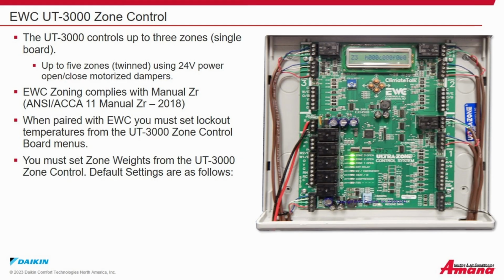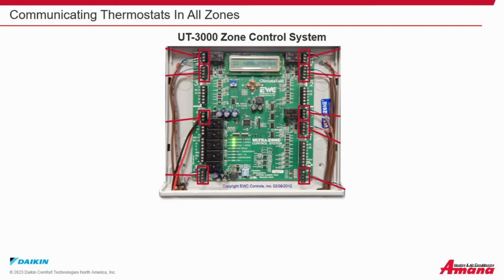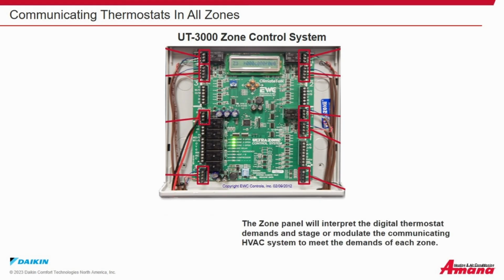Default settings are as follows. For a 3-zone, 70%, 15%, and 15%. For a 2-zone, 60%, 40%. Communicating thermostats in all zones. With the UT3000 zone control system, the zone panel will interpret the digital thermostat demands and stage or modulate the communicating HVAC system to meet the demands for each zone.